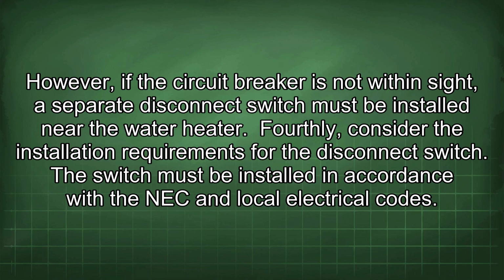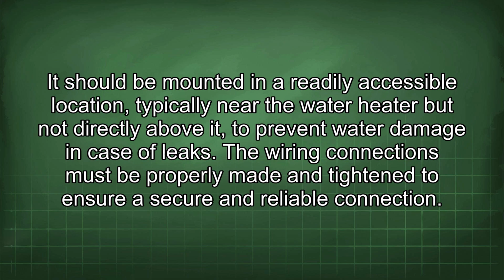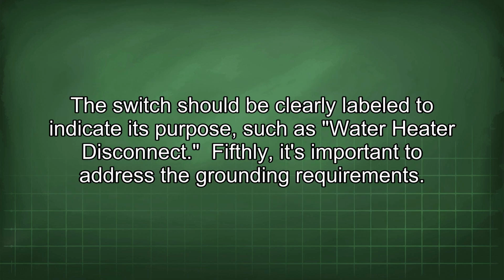The switch must be installed in accordance with the NEC and local electrical codes. It should be mounted in a readily accessible location, typically near the water heater but not directly above it, to prevent water damage in case of leaks. The wiring connections must be properly made and tightened to ensure secure and reliable connection. The switch should be clearly labeled to indicate its purpose, such as water heater disconnect.